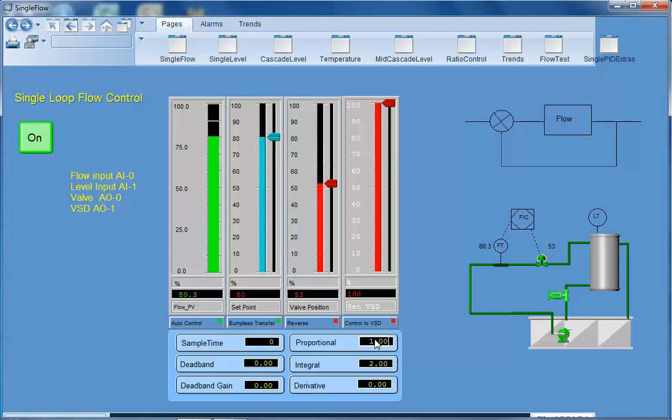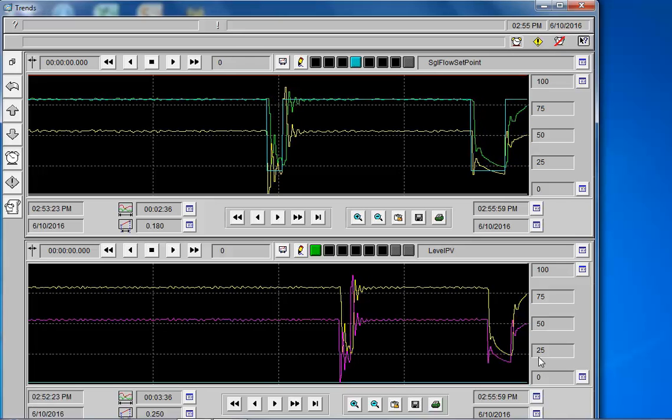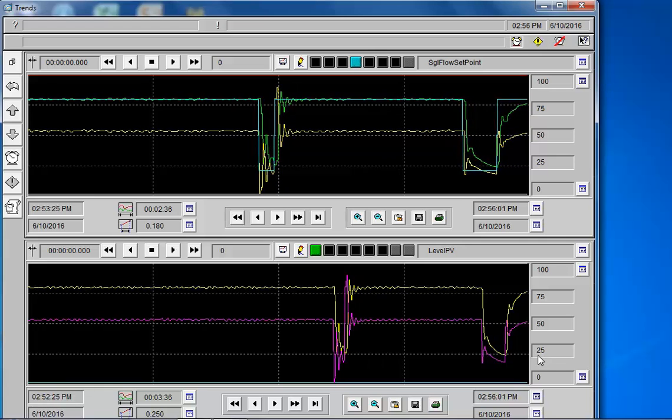We might start by decreasing our amount of P, because increasing P moves to oscillation, decreasing I moves to oscillation. So let's halve that to 0.5 and oscillate through our 20 to 80% operating range and see what the output is. Once again, letting it settle. Going back to our trend screen, now we're seeing an output quite different.